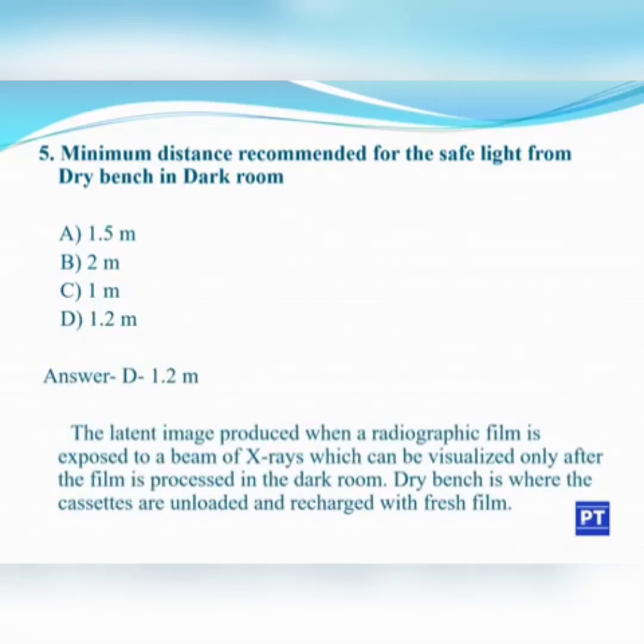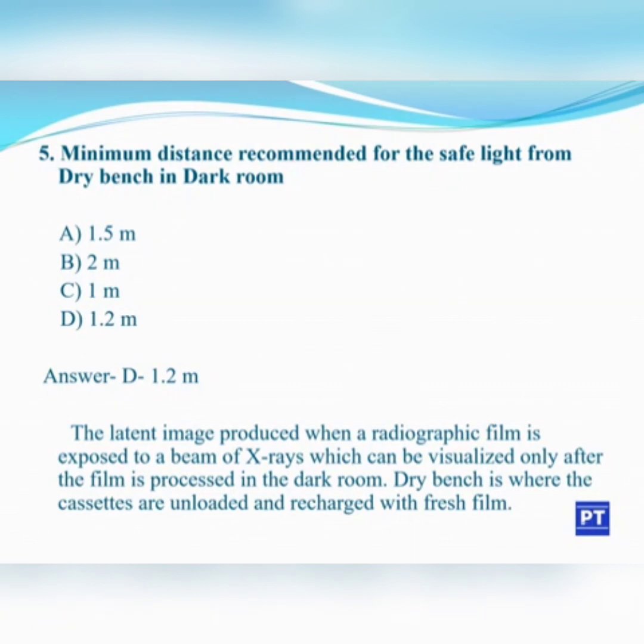The latent image produced when a radiographic film is exposed to a beam of X-rays can be visualized only after the film is processed in the dark room. The dry bench is where cassettes are unloaded and recharged with fresh film. Inside the dark room there is a dry bench, wet bench, and a safe light. The minimum distance of the safe light from the dry bench is 1.2 m.